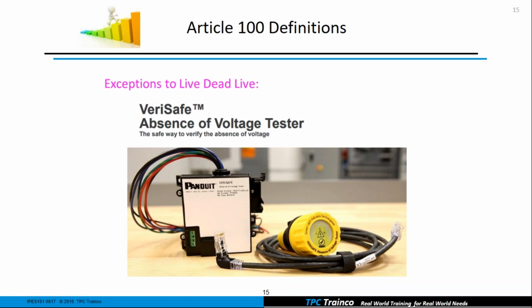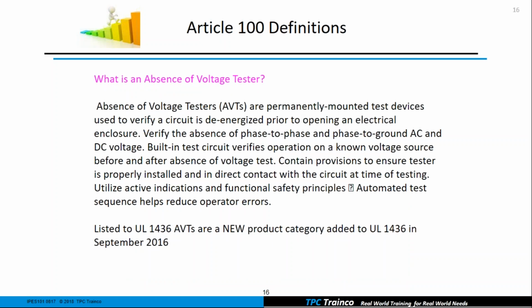So that is excellent. That could save our technicians from having to put on a lot of extra personal protective equipment. And to give you a little bit of idea about these, they are permanently mounted test devices, and they can do AC or DC. And really, it takes away the chance of having an operator error. They are listed. The UL standard for these is 1436, new product category, and they've been out now about a year. So NFPA 70E recognized those, and that's a great proposal.